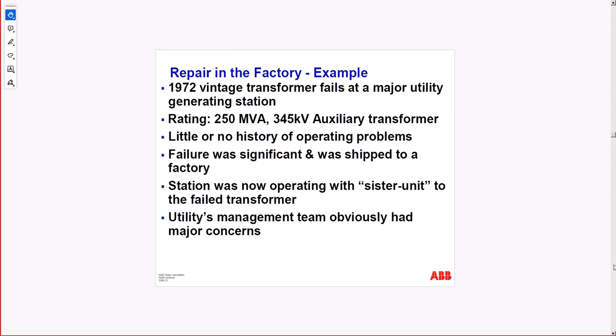Well, we repaired in Pickering. We had a severe dead short on unit 7 back in 2006, I think, that went a little bit sideways. The power was energizing the main output transformer with a dead short, because the safety grounding leads were not removed. They were declared removed, but they were not. So the whole 500 MVA three-phase transformer moved a few feet, elongating the bus bars, and that was very dangerous.